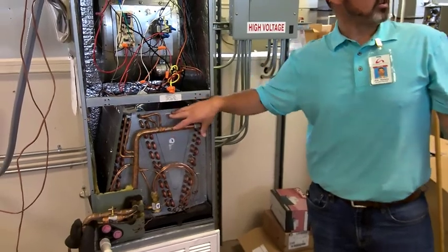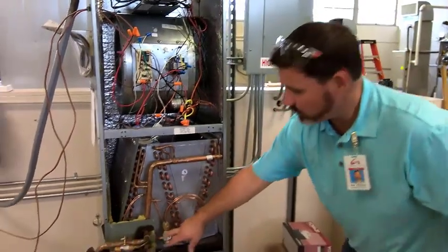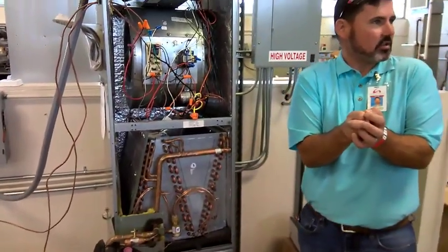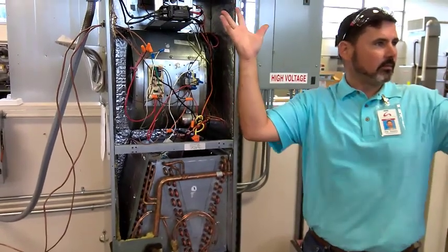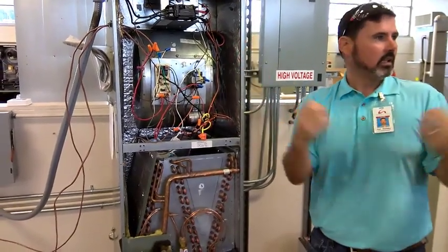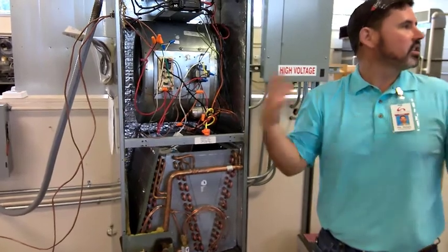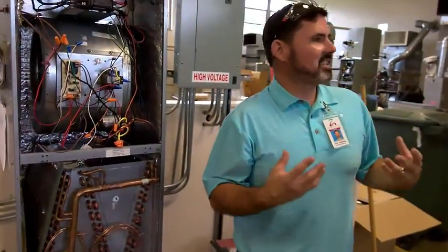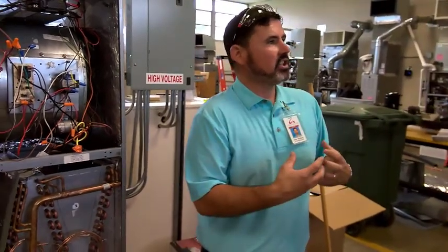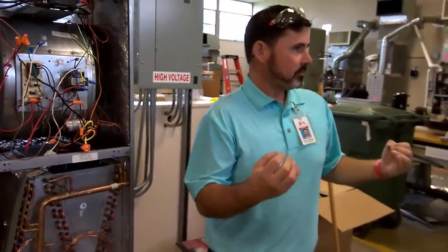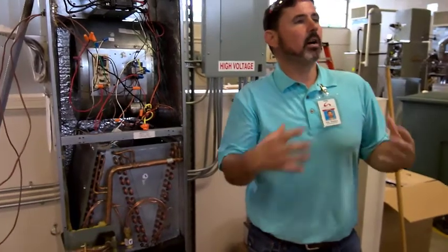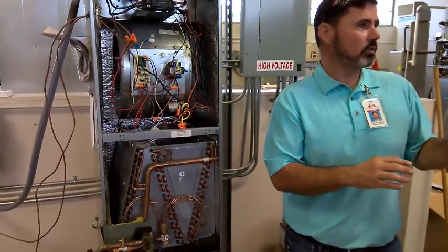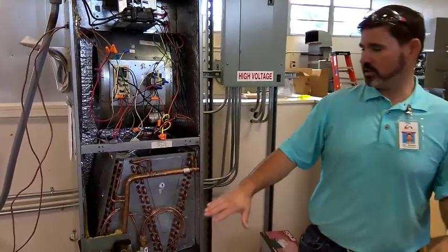The reason that's called an evaporator is once that liquid refrigerant hits that very low pressure, now it's allowed to flash off into a vapor. So my liquid refrigerant is turning into a vapor. In order for that liquid to turn into a vapor, it has to have energy. All right? It's going to use heat energy. Heat is a type of energy, and heat moves from hot to cold. Two golden rules that will help us understand everything going on here.